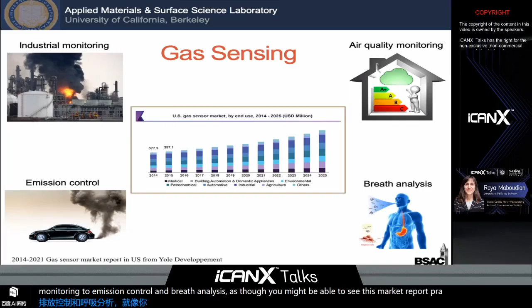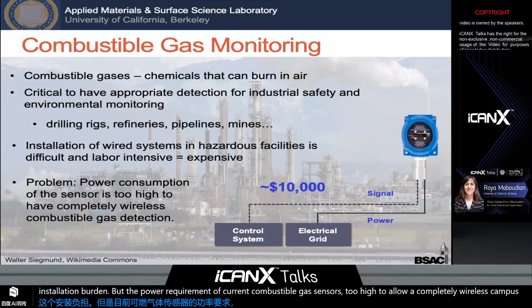Combustible gases such as methane, propane, or hydrogen can burn when their concentrations reach a certain value in air, the so-called lower explosive limit, LEL. It is critical to have appropriate detection for industrial safety and environmental monitoring. Current wired systems are difficult to install and expensive. Battery-powered wireless monitors would eliminate this installation burden, but the power requirement for current combustible gas sensors is too high to allow completely wireless combustible gas detection.